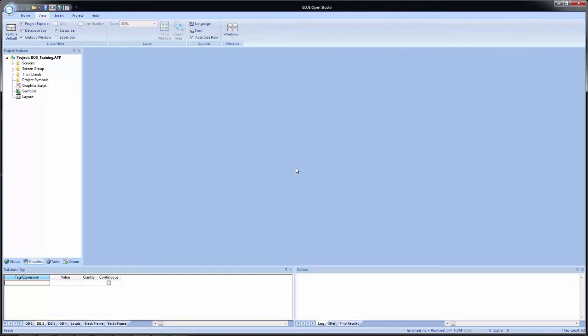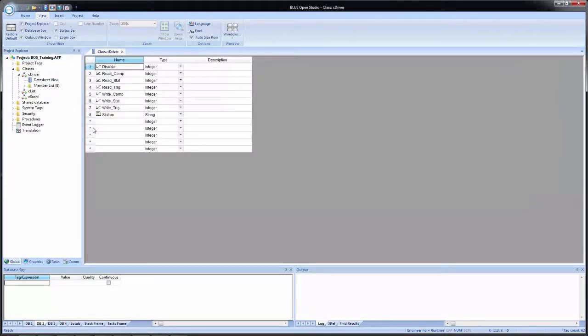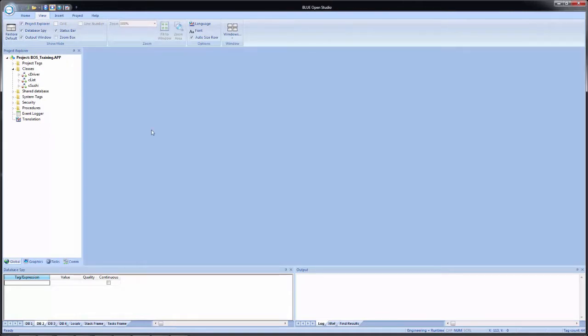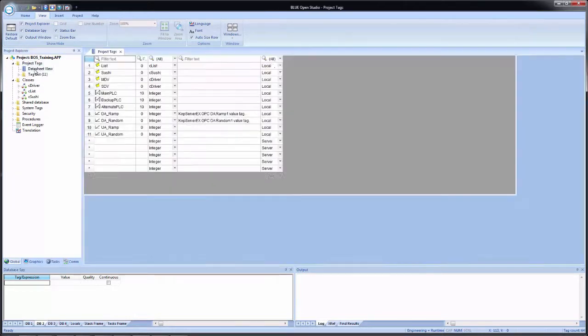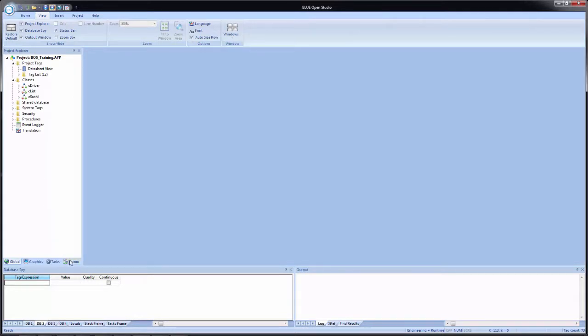We'll now configure two DDE communication worksheets. The first will be to KepServer. First I will need to add a new member to our driver class, so I will go to the global tab, expand classes, and open the datasheet view for the cDriver class. At the bottom, I will add a CONN name and leave the type at integer. Now I will open my project tags database and add a new tag called DDE underscore KEP, set the data type to cDriver, and set the scope to local.